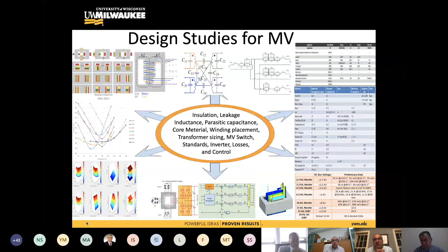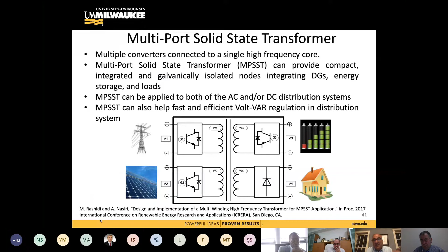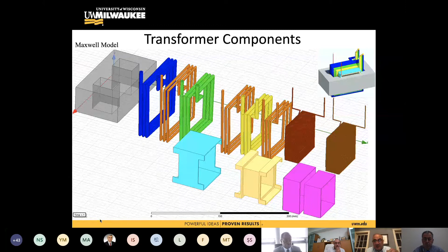And then, of course, you go through a complex process, as I mentioned, from the transformer design, from the converter design, from the topology. Then you have to go through all the creepage distance, insulation, and so forth, especially in the case that you have a medium voltage. For this case, our medium voltage is 4160 volt, 3-phase AC. And the design of the transformer has many components, all the windings, all the sheets that go in between them, and of course, all the practical cases there.